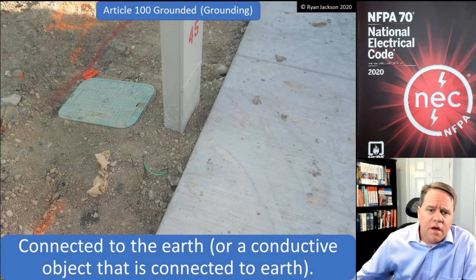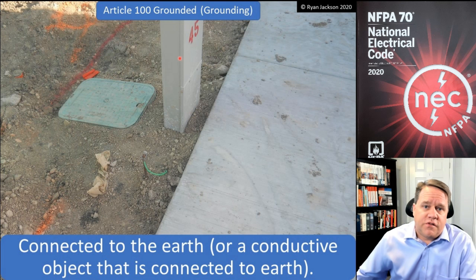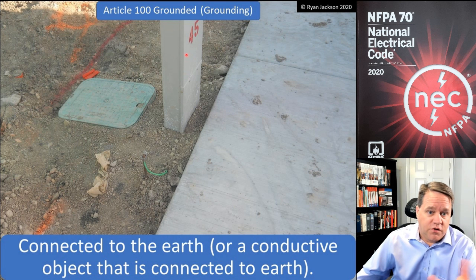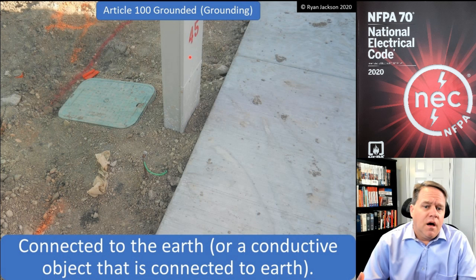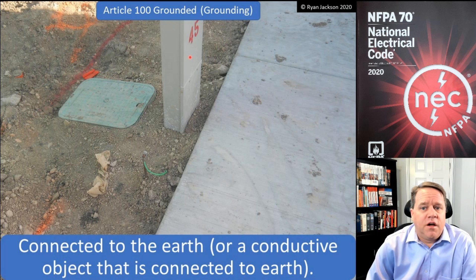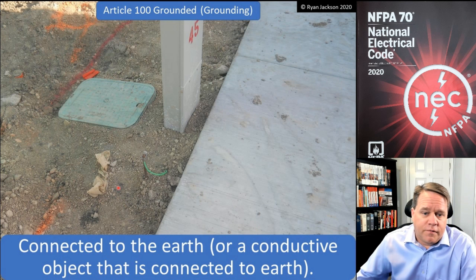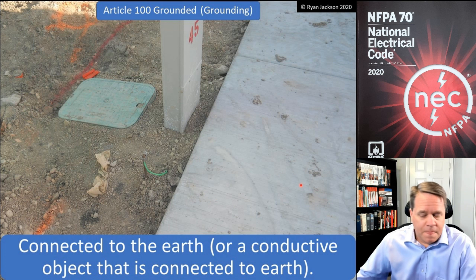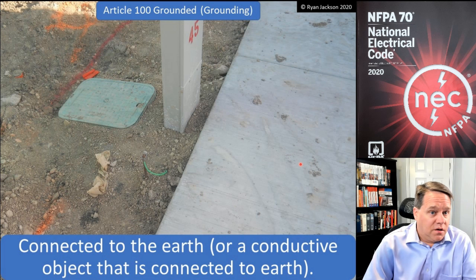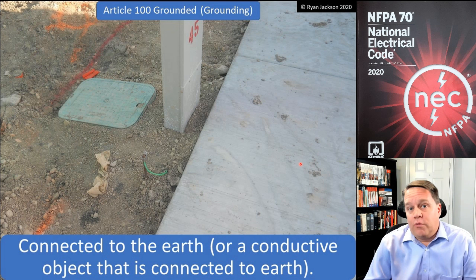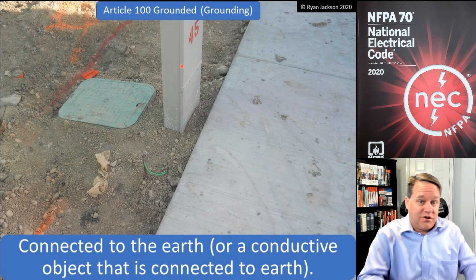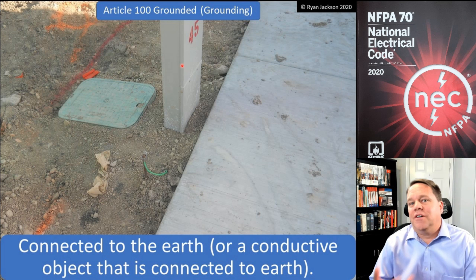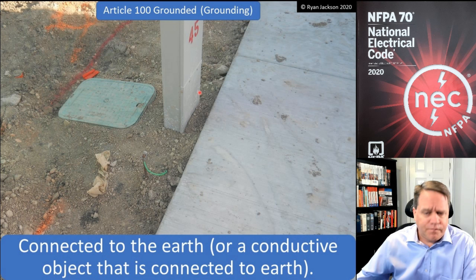Ever since 2008, these terms are so much better. Here's a temporary pedestal for a house being built. This is service equipment by definition — the utility goes straight into this enclosure, there's a meter and circuit breakers. Per 250.24(A), that equipment has to be connected to a grounding electrode and grounding electrode system, which we have here in the form of this ground rod. We connect the metal parts to the grounding electrode with a grounding electrode conductor — much more descriptive than just saying that metal thing has to be grounded.